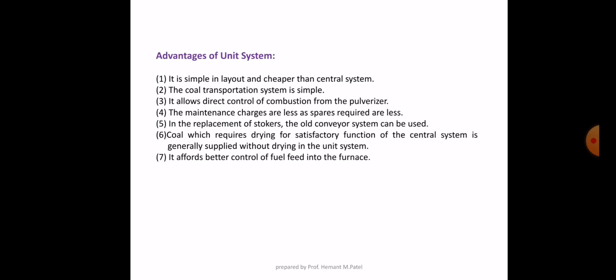Advantages of the unit system: It is simple in layout and cheaper than the central system. The coal transportation system is simple because the coal is introduced directly into the coal bunker, passing into the feeder and then the coal mill. It allows direct control of combustion from the pulverizer. The maintenance charges are less, space required is less. In replacement of stokers, the old conveyor system can be used. Coal requiring drying for the central system is generally supplied without drying in the unit system. It affords better control of fuel feed into the furnace.